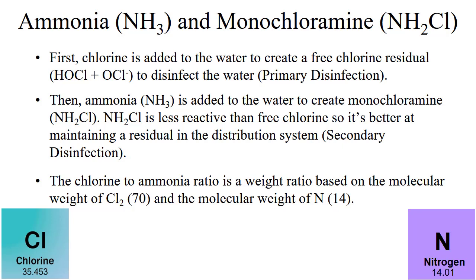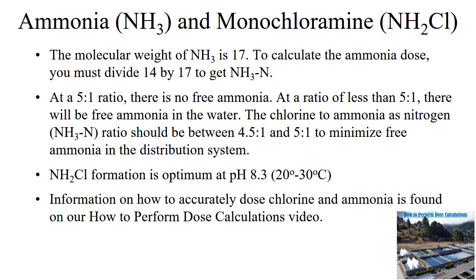The amount of ammonia fed at a plant is based on the chlorine-to-ammonia-as-nitrogen ratio. This ratio is based on the molecular weight of chlorine, Cl2, which is 70, and the molecular weight of nitrogen, which is 14. The molecular weight of ammonia is 17. To determine the nitrogen portion of ammonia, divide the molecular weight of nitrogen, 14, by the molecular weight of ammonia, 17, to get ammonia as nitrogen.